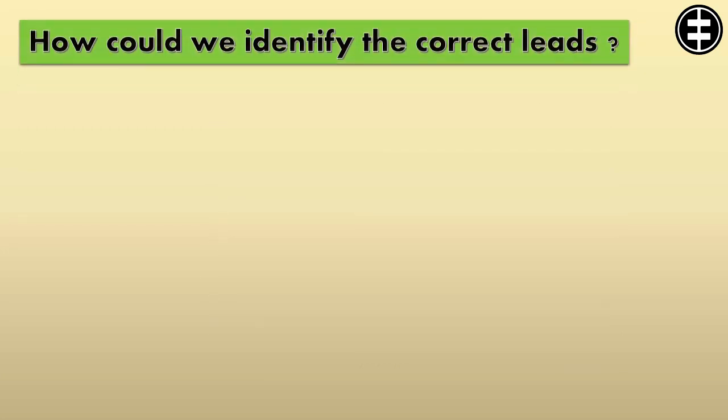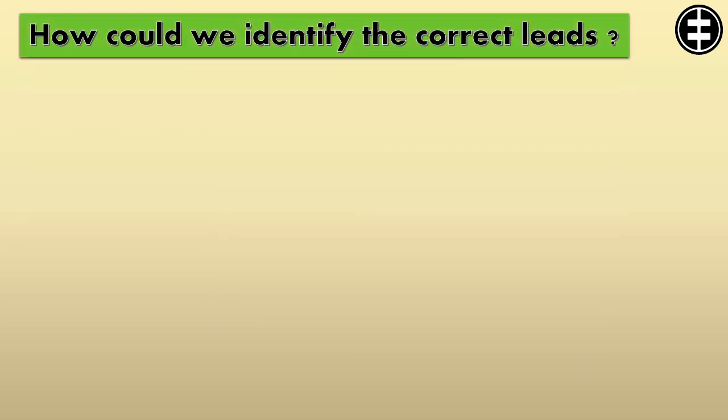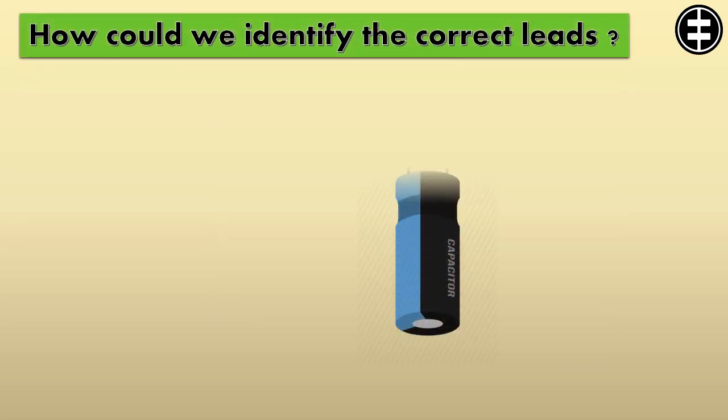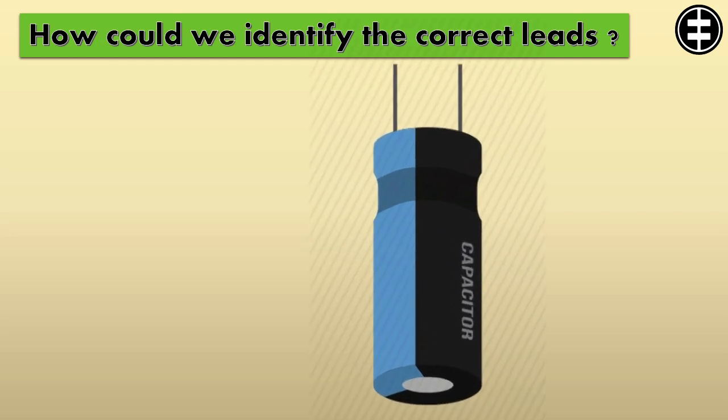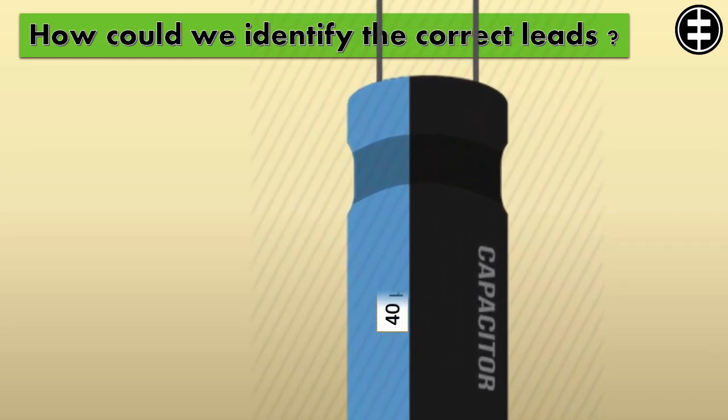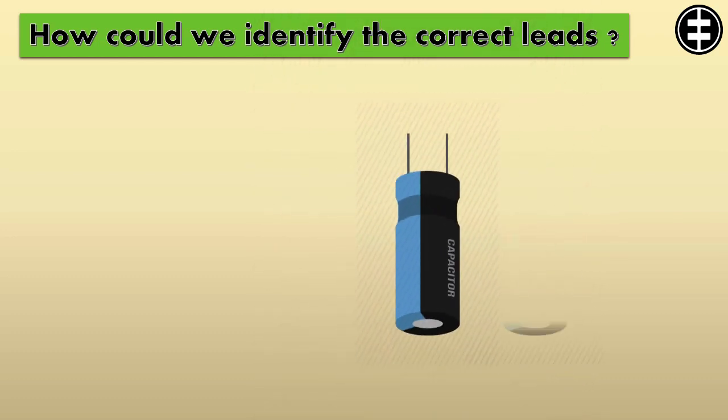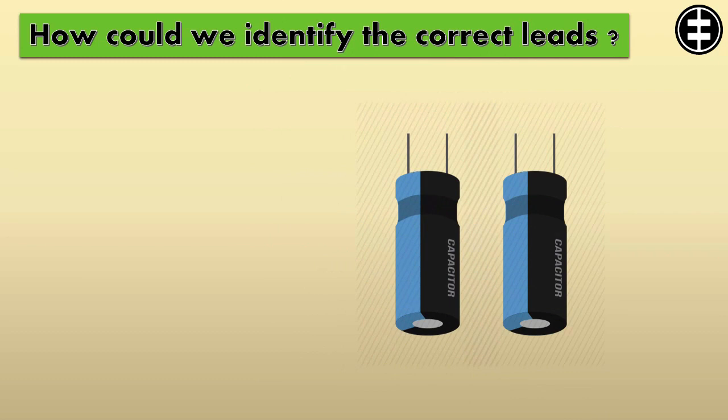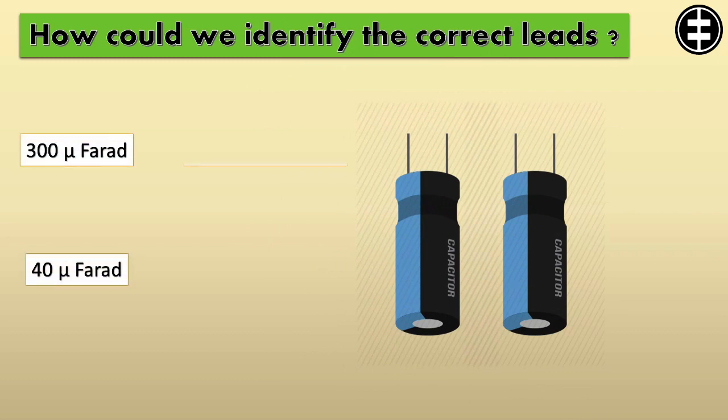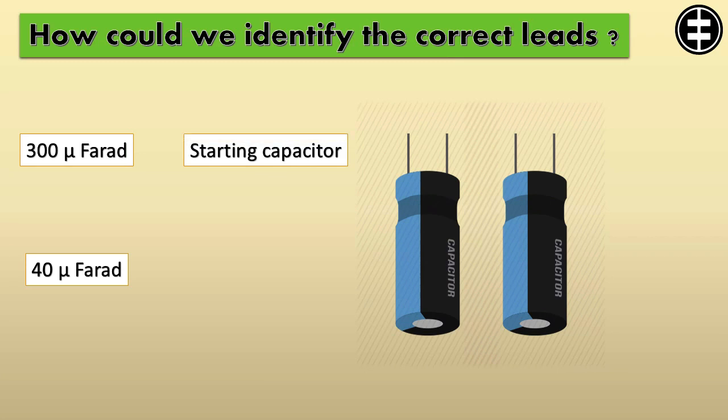How could we identify the correct leads? First check the capacitor's microfarad values. Normally it's printed on the capacitor. In our case we have 2 capacitors, one is 300 microfarad and the second one is 40 microfarad. Normally the higher microfarad capacitor is the starting capacitor.